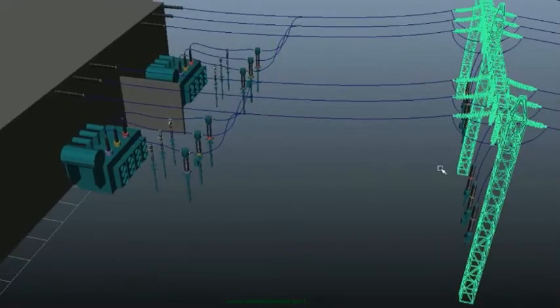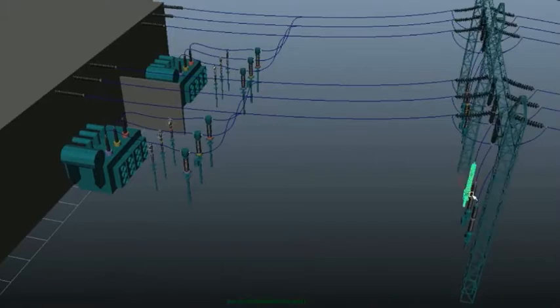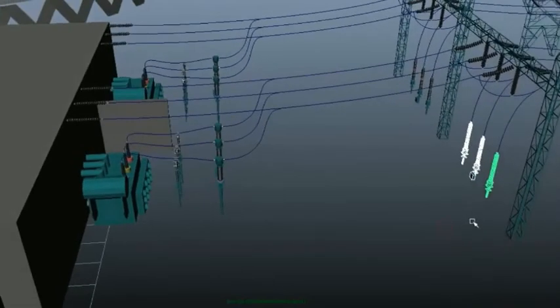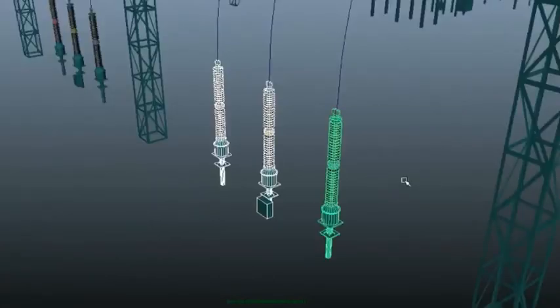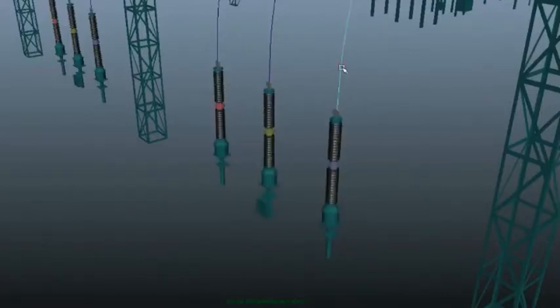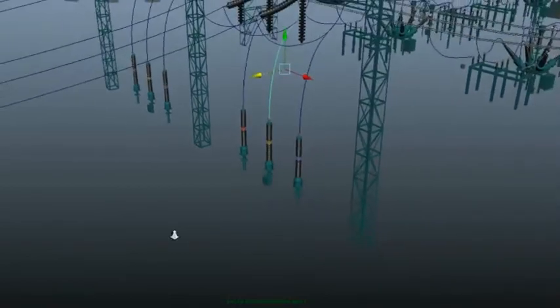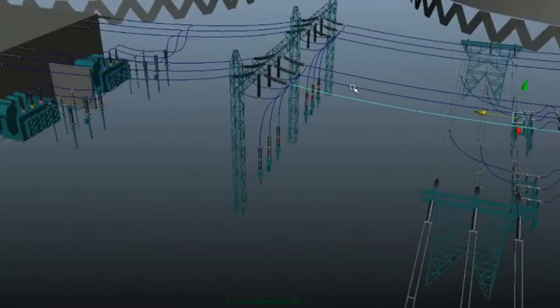Voltage transformers are installed here to measure how much voltage is on the line conductor due to the transformer. These look like current transformers, but these are connected in parallel to the line conductor. This means that one of their terminals is connected to the line terminal while the other terminal is connected to the earth. In the secondary circuit of each transformer, a voltmeter is connected so that we get regular information of the voltage of each phase.